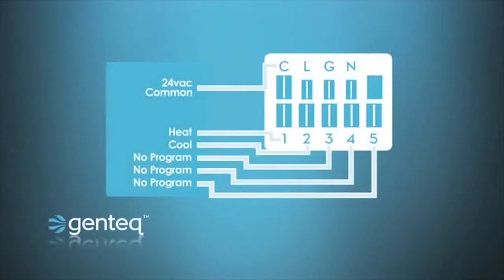So let's look at an example of a package system using X13. This happens to be a gas and AC package system, and we notice that there is a heat and a cool tap sending voltage to the motor. However, we also notice that there's 3 of the taps on the motor that say no program. That's because the manufacturer does not have to program all 5 taps of the motor.